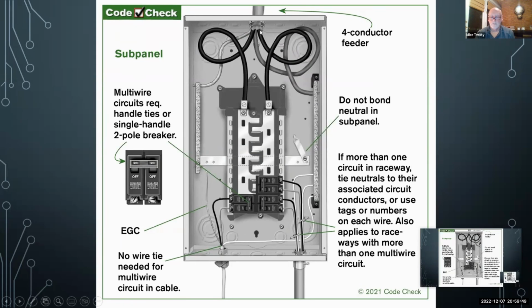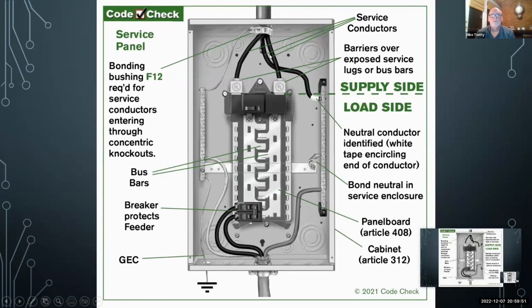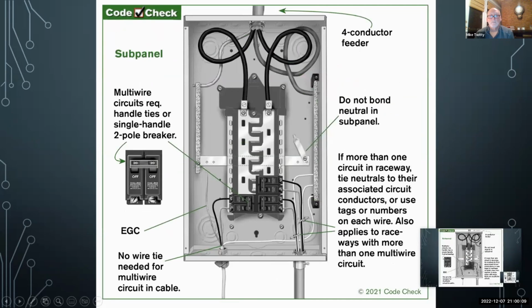This is a 4-wire feed. This is a service panel. This was a 3-wire feed. That's all you need in the service panel. The neutral takes care of bonding the path back to the transformer for the equipment grounding in the event of a fault. So back to the sub panel. You don't bond the neutral in the sub panel. This is now the neutral bar for neutrals only. The equipment grounding bar for equipment grounding conductors only. They're separated in the sub panel. Like I say, it's a 4-wire feed, which you're going to see in a sub panel.